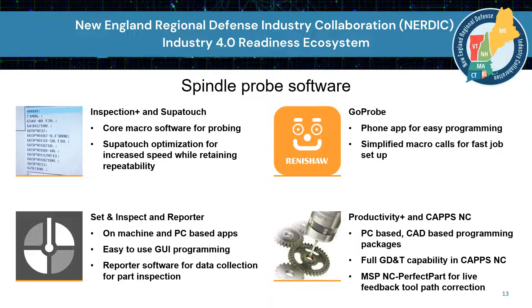The Set and Inspect, as I mentioned, this is an image that you would typically see from the GUI. These are used to call single cycles very quickly at the machine tool control. You've got basic functionality like bores and bosses, pockets and webs, internal and external corners, lines, planes, rectangles, and we also have the ability to do rotary axis updates. So if you're measuring whether or not your part is aligned correctly on, say, a C-axis, you can probe a few points on the part and have the machine automatically set your 0 point.